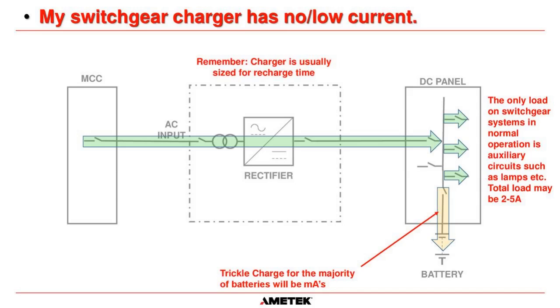And the next thing that I hear a lot: my switchgear charger has low or no current. Remember, for a switchgear system, there is very little load in normal operation. Really, all your charger is doing on a switchgear system is keeping the battery charged. There may be some lamps on the switchgear system that they need to power, and maybe some auxiliary circuits that may be powered off it. But usually there's about 2 to 5 amps maximum on a switchgear system in normal operation.